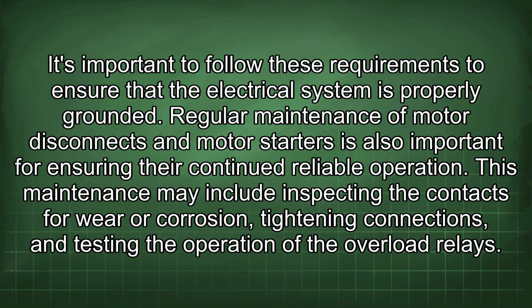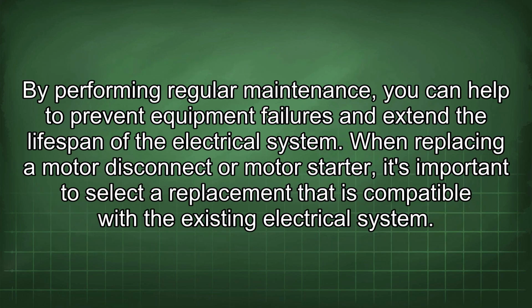Regular maintenance of motor disconnects and motor starters is also important for ensuring their continued reliable operation. This maintenance may include inspecting the contacts for wear or corrosion, tightening connections, and testing the operation of the overload relays. By performing regular maintenance, you can help to prevent equipment failures and extend the lifespan of the electrical system.